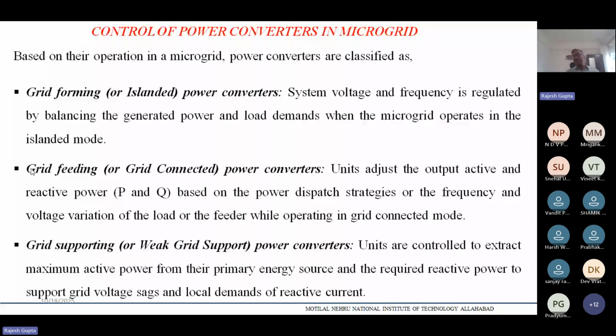In grid following mode, frequency is governed by the grid frequency. In grid forming, frequency is decided from the stability point of view. Whereas in grid feeding mode, the frequency is decided by the grid only, so we normally use a phase lock loop in grid feeding inverters. We can't touch the frequency of the grid; the only thing we can do is change the active and reactive power and which side it goes. That's grid feeding mode.